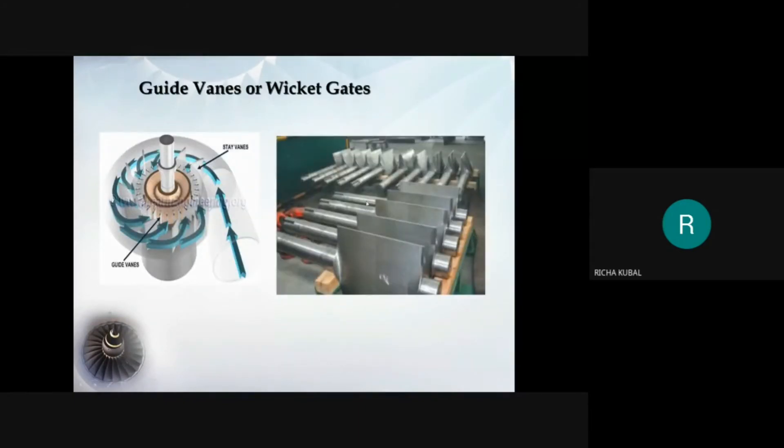These are the wicket gates, also known as guide vanes. These vanes are fixed in position but they can rotate around their respective pivots. The function of guide vanes is to direct the water from casing to moving vanes of runner without shock at inlet. Hence, to achieve smooth and shockless entry to the runner, the velocity of water must be kept tangent to the inlet tip of runner.